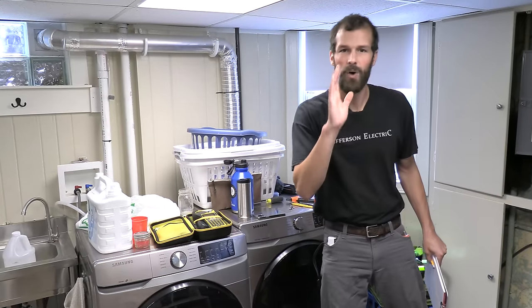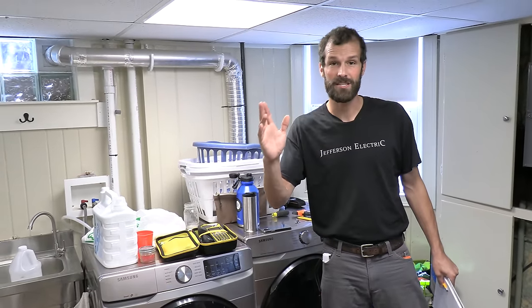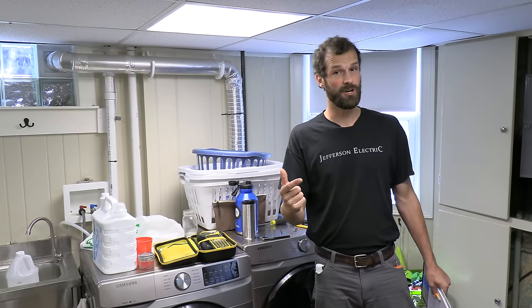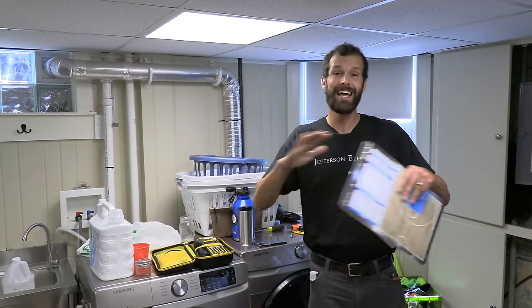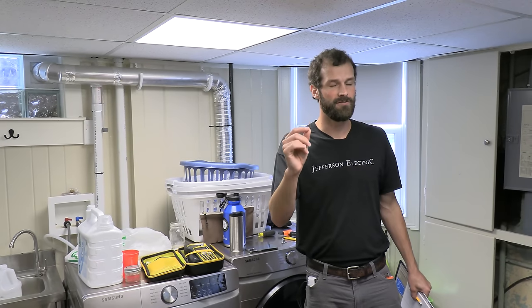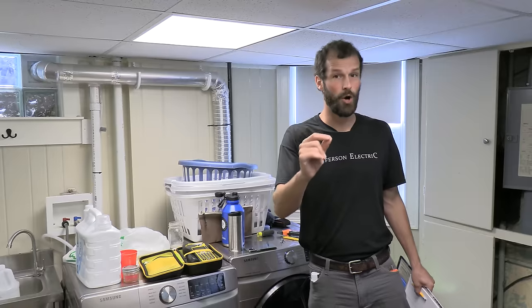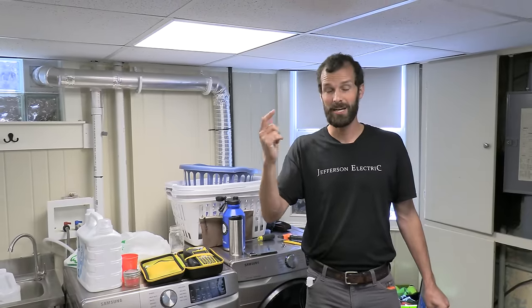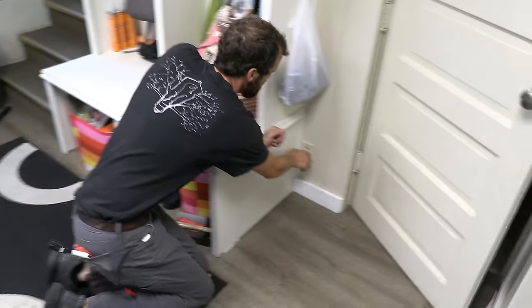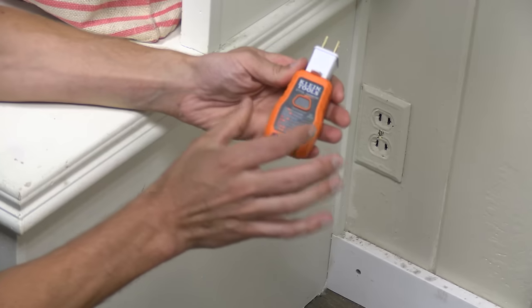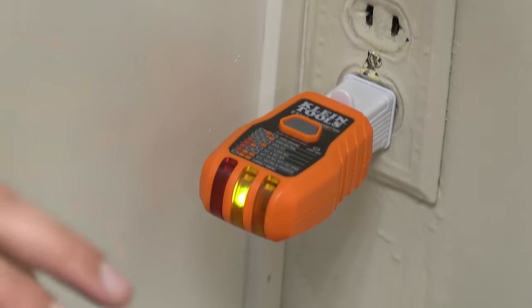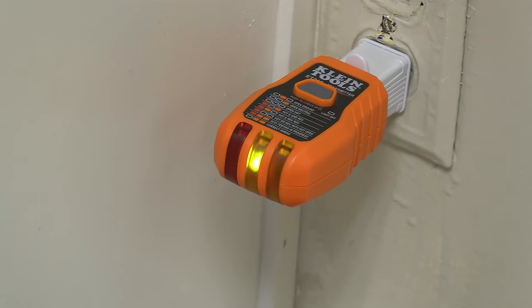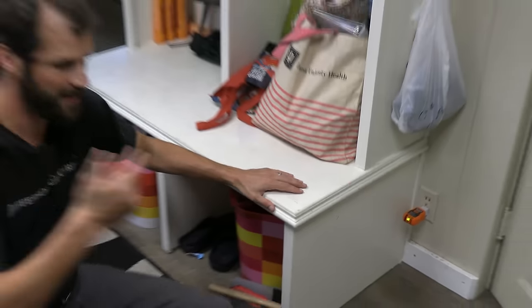If this was a gas dryer, it would be on a 15 amp plug like the one we saw or something similar. And let me say, wire gauge matches breaker size. And if you have trouble with a tripping circuit in your house, you absolutely cannot, except in very, very rare circumstances by qualified personnel only, upsize the breaker to prevent it from tripping. I'm still in the mudroom. And I'm checking over here. I've got a two prong receptacle. So I've utilized my adapter that came with my toner kit. I'm plugged in and obviously right on the other side of the mudroom, different circuit. So I'm going to have to go through the process of toning the panel again to find that one. And at this point, I'm just going to go room by room to avoid running a million stairs by the end of the day.